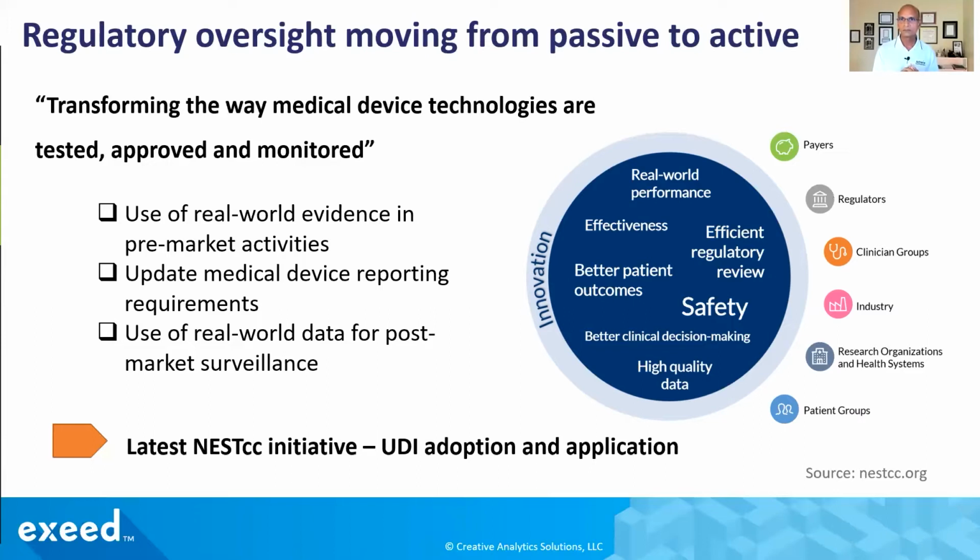And it could vary from a brand new device where you just released it, you want to be very active and go out there frequently and seek information about how that device is performing, where if you have had something on the market for 5 years or more, you may have a good, stable set of information. And what you want to do is just watch for those indicators that something has changed. So it's not as intense as with a brand new device. So that was in the Clause 10 of 14971.